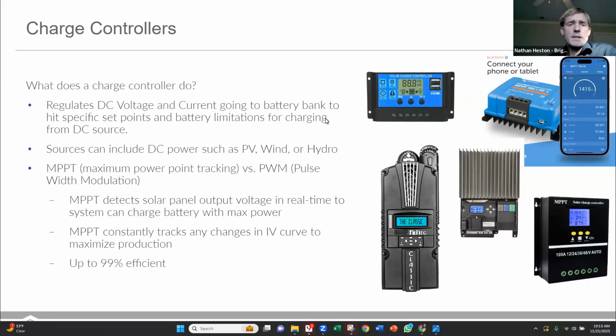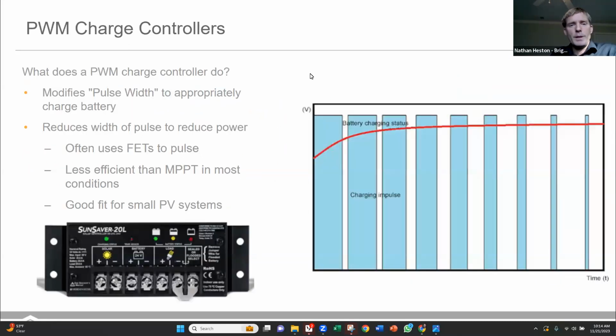And these MPPTs can take about 99% of the power output out of your solar array and use that to charge batteries. They're highly efficient. You, of course, lose some power in the equipment. About 1% of it is turned to heat, hence the fans and the cooling fins on this equipment. But additionally, the battery itself has an internal resistance, which produces some heat, and you lose some energy there. But still, round-trip efficiencies, you can get as high as 92, 94% for good DC-coupled equipment.